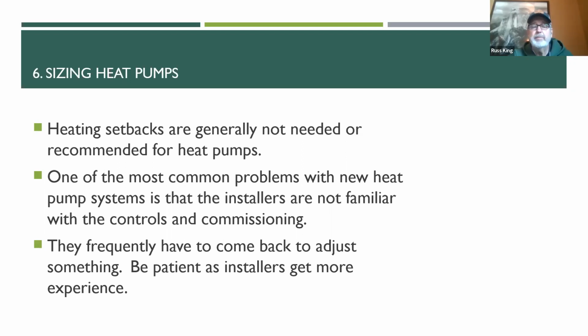One of the most common problems with new heat pump systems is that the installers are not familiar with the controls. A lot of installers are used to installing old style equipment, and they get these fancy new units in there and they're not super experienced with them. And there's a lot of little knobs and settings that have to be set very precisely for them to work. And so that's probably one of the biggest complaints we're having right now: the installers are not reading the instructions quite as well as they should. And so just be patient.